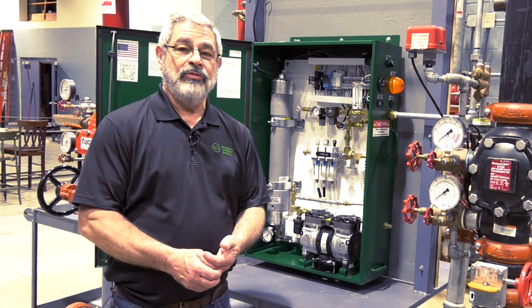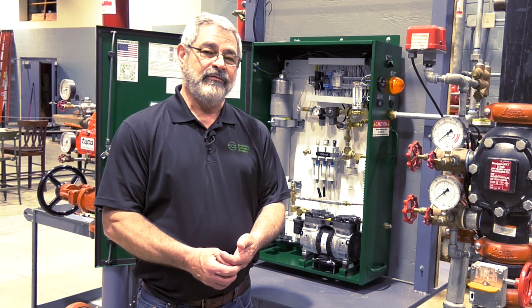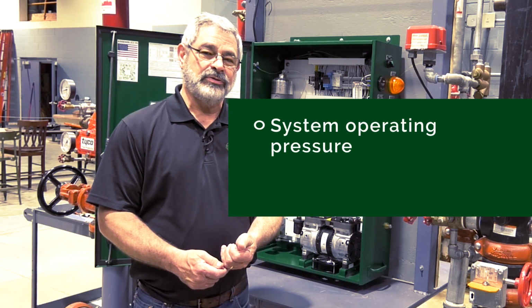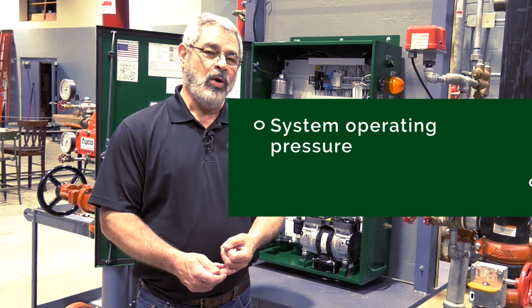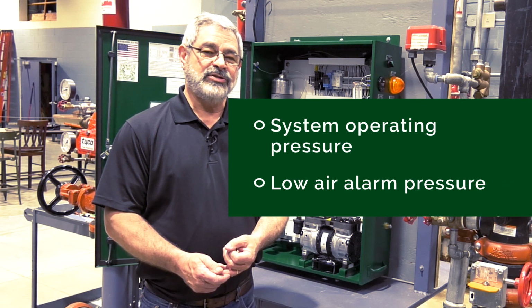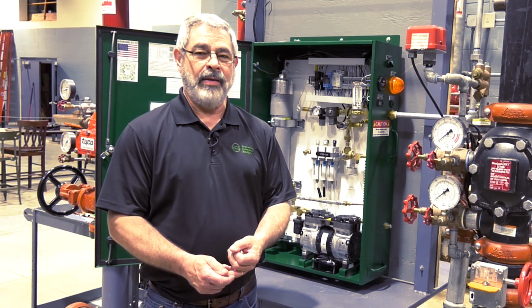The reason we need to know that is our nitrogen generator needs to turn on 5 pounds below the operating pressure of the sprinkler system. We also have to make sure that our turn on pressure is above the low air alarm. So the information we need is the operating pressure of the sprinkler system and the pressure that the low air alarm is coming in, and make sure we can operate within those two parameters.